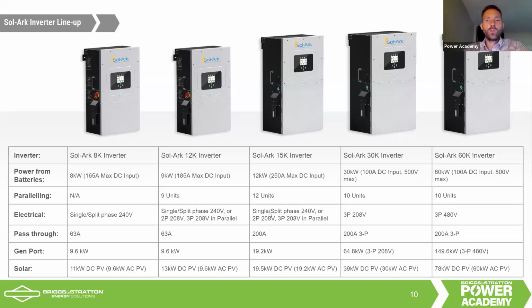You can do 3-phase, you can do single phase, you can do split phase, which we often think of as single phase here in the US, but that's where you have two 120s relative to a neutral. So you can also do 2-phase 208. So I actually run a 15K inverter in my shop that's running 2 phases of 208. So 2 phases of my 3-phase in the shop. So with 2 inverters, you can do unbalanced 3-phase. With 3 inverters, 6 inverters, 9 inverters, 12 inverters, you can do 3-phase balanced 208 in the Y configuration with the Sol-Ark inverters.